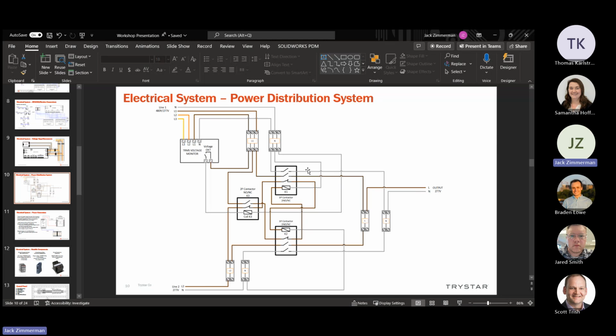Basically, the general concept is it favors line one power pass through because that's our utility line. But if line one has some kind of problems, it will switch over to line two immediately and lock it in place. If both lines are active, line two or line one will pass through. So it's basically just a mini ATS within the ATS, the way I look at it.